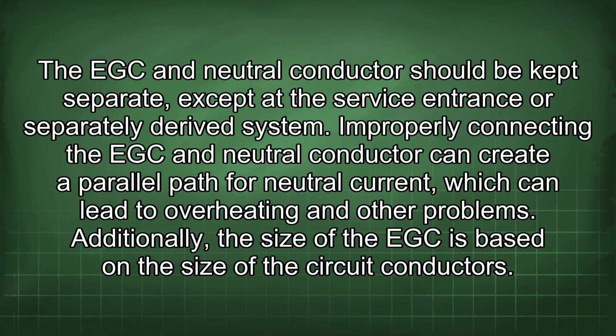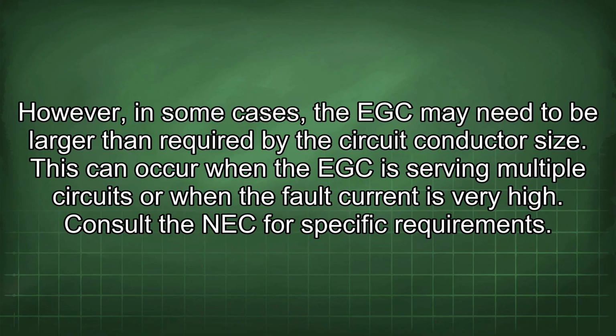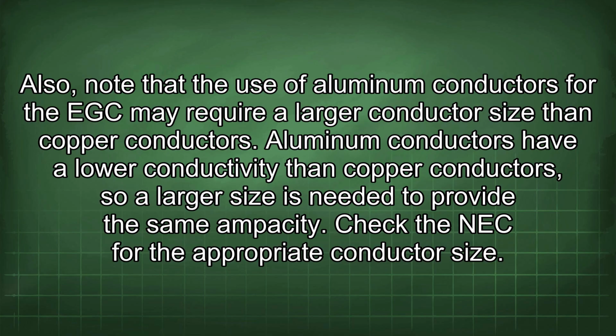and other problems. Additionally, the size of the EGC is based on the size of the circuit conductors. However, in some cases, the EGC may need to be larger than required by the circuit conductor size. This can occur when the EGC is serving multiple circuits or when the fault current is very high. Consult the NEC for specific requirements. Also, note that the use of aluminum conductors for the EGC may require a larger conductor size than copper conductors. Aluminum conductors have a lower conductivity than copper conductors, so a larger size is needed to provide the same ampacity. Check the NEC for the appropriate conductor size.